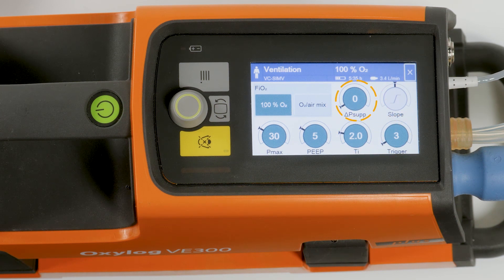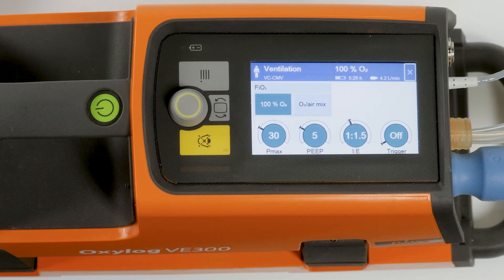rise time (Slope), and the pressure support delta P. When the trigger sensitivity is activated and set, the mandatory breaths are synchronized with the patient's inspiratory efforts. A low value corresponds to a high sensitivity.